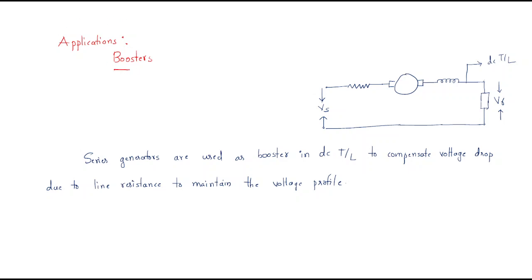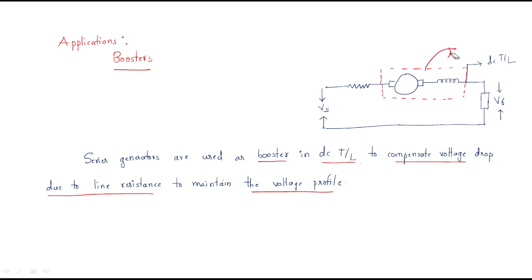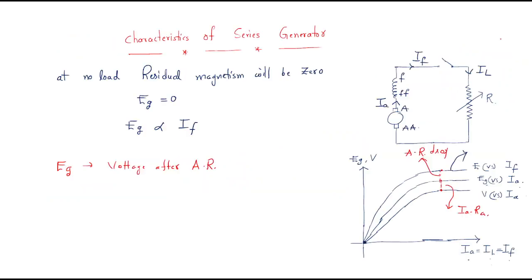The series generator is primarily used as a booster in DC transmission lines to compensate for the voltage drop due to line resistance. In DC lines, resistance drops are unavoidable; by connecting a DC series generator in series with the line, the voltage profile is maintained constant. This is the main application of the DC series generator, concluding our discussion of both DC shunt and series generator characteristics.